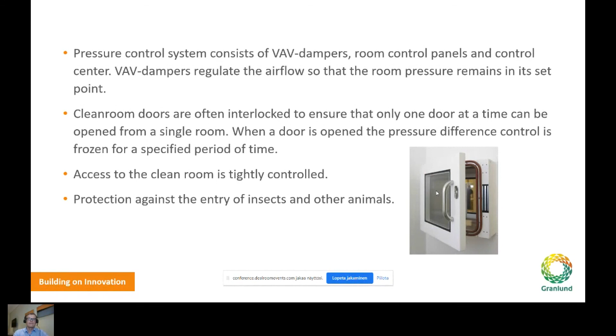Then this monitoring system, clean room compliance with its given requirements must be demonstrated by regular measurements and documentation. And recently it has become customary to produce documentation of compliance with a validated environmental monitoring system. And this monitoring system is totally different than the building automation system, which controls the air volumes and pressures. This only monitors and collects the data from pressure differences, particle counts, temperature and humidity. And normally the system consists of room sensors and particle counters.